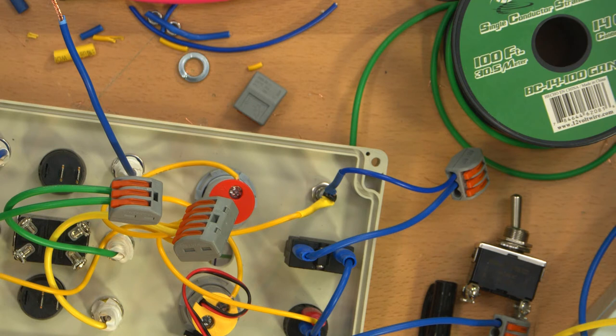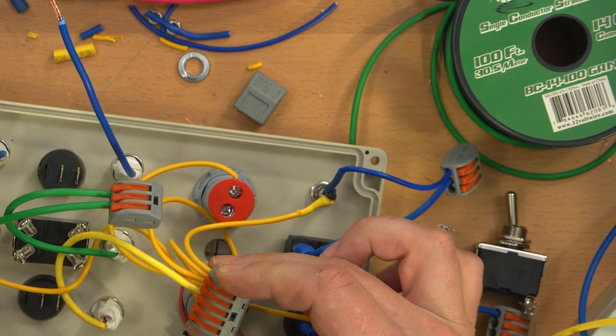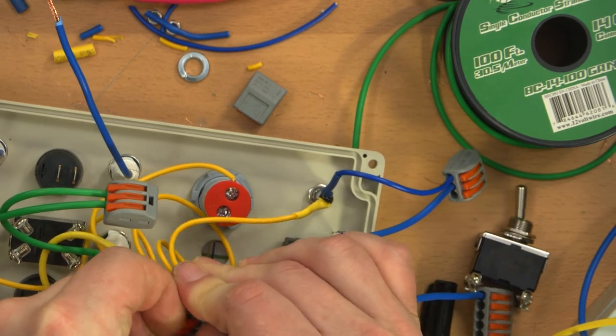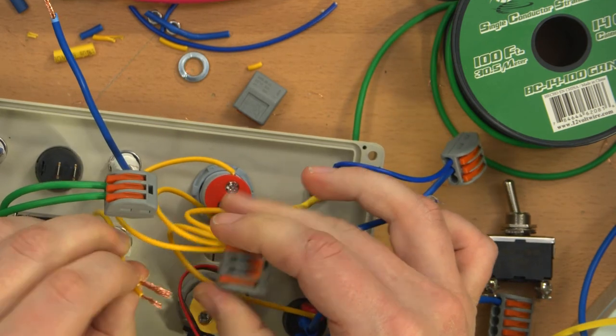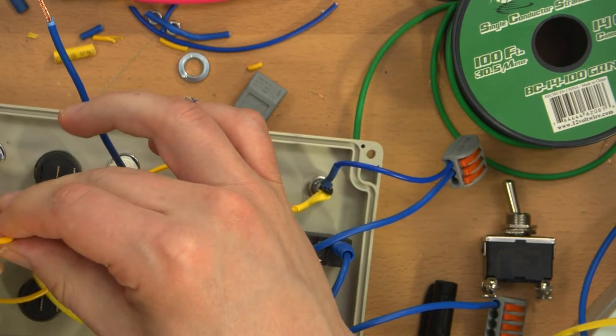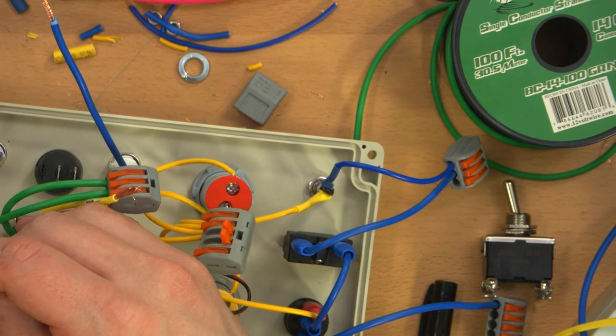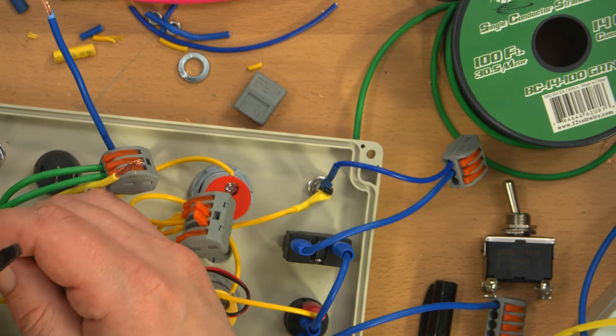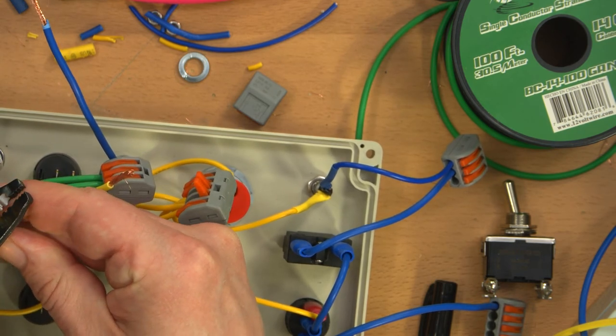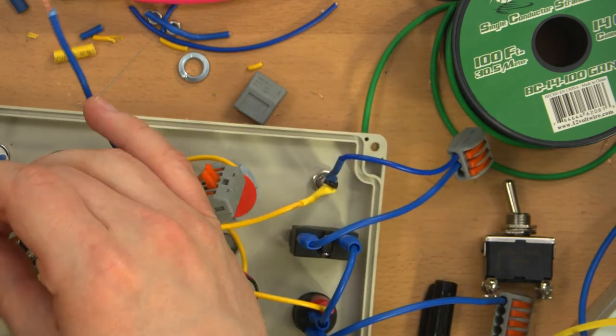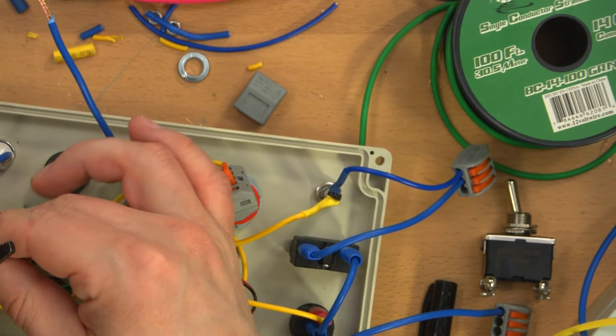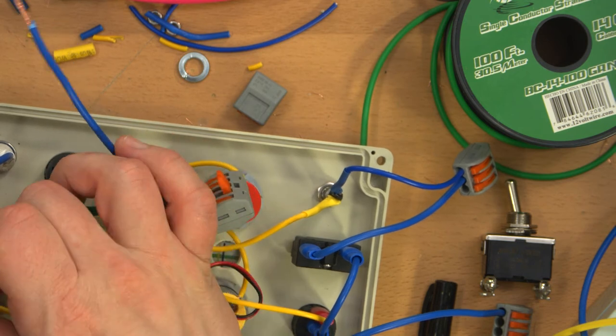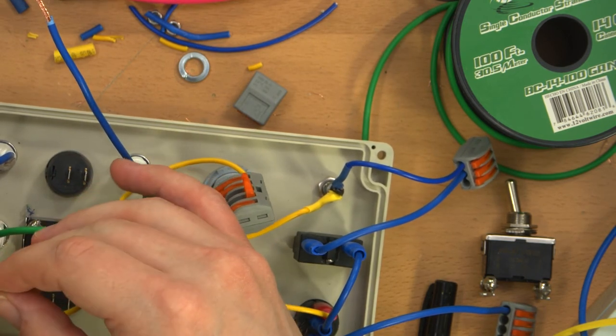I mean, I could jumper out of that five-position to another three-position. I don't want to fill this entire box with Wago connectors. I mean, I can, but I'm not going to. So what I can do is maybe combine this thinner wire with this fatter wire. Just re-strip them to get them extra tight to fit into the Wago connectors' orifice. I mean, honestly, I could also chop a few strands off of here if it won't fit. Because, again, this whole thing is going to have overcurrent protection at three amps. So I don't even need 14-gauge wire, it's definitely overkill.